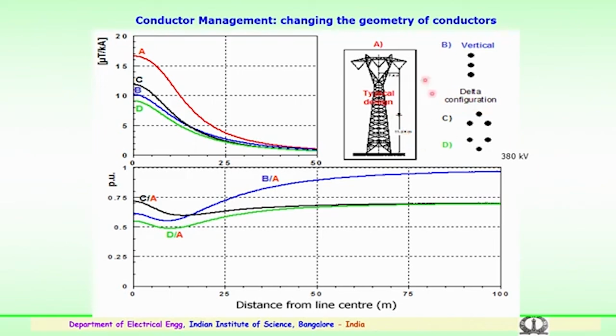You can see a small example here, a typical example of the design of a vertical type of tower or a delta configuration type, or how the conductors are managed and connected. This will be helpful. So, various options have been shown here. See for example, this is one type of arrangement where the conductors have been connected, and this is the clearances. B is the vertical conductors placement, as shown here. Third being the delta configuration in a rectangular equilateral triangle type, and D being the inverted equilateral triangle.